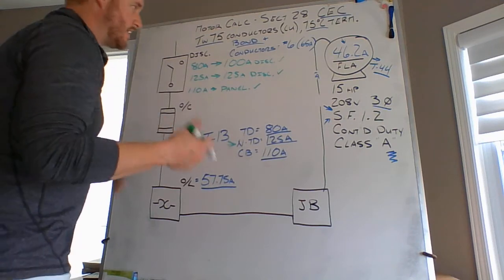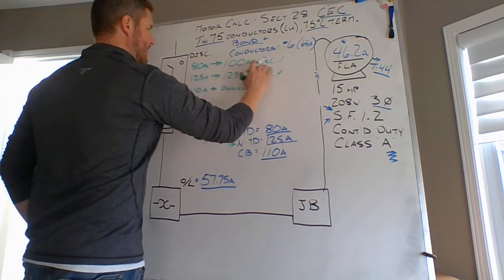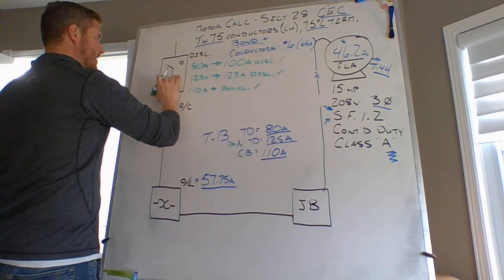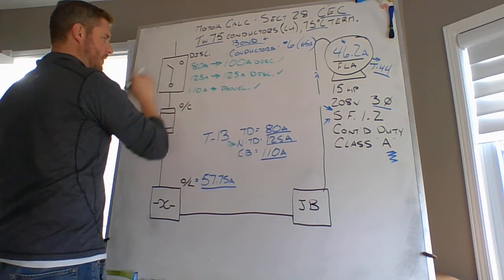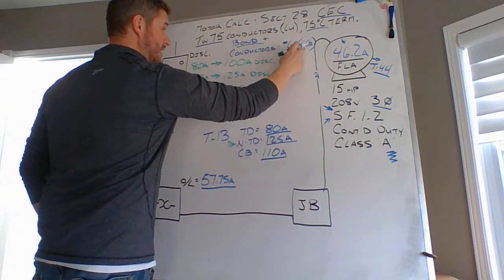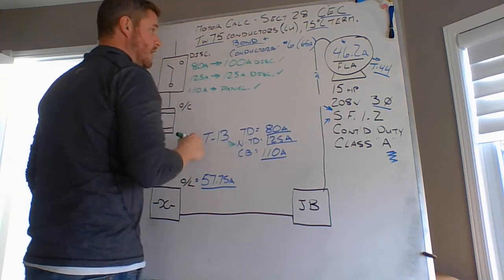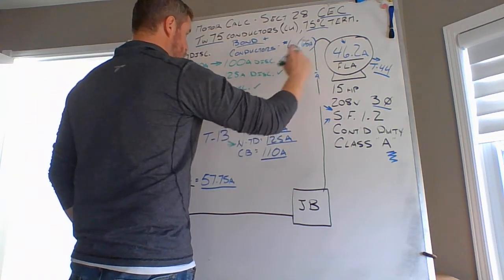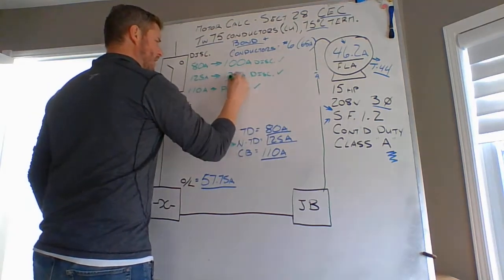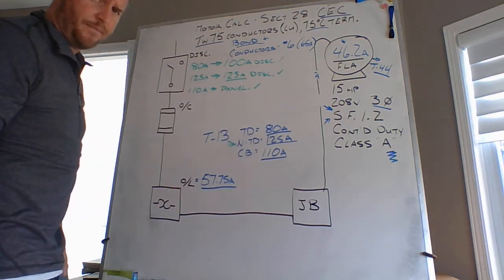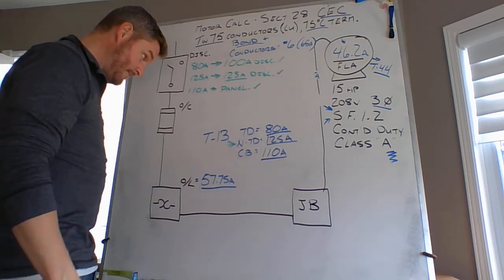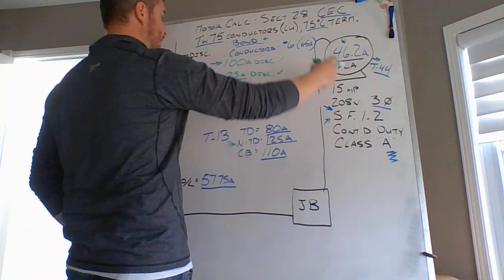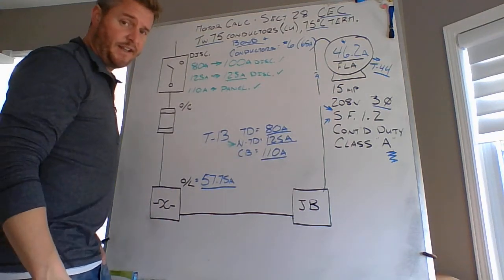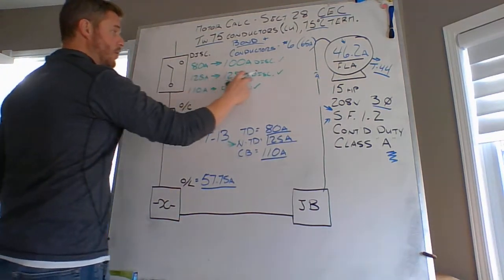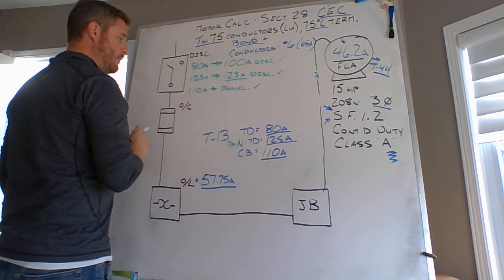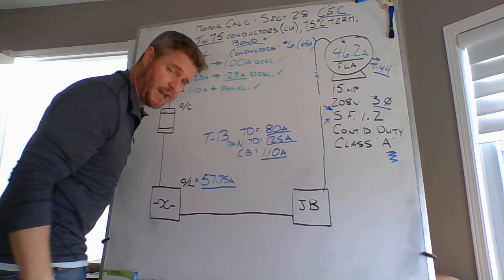But you're actually going to sit there and tell me that you're going to put in a 100 amp disconnect with 80 amp fuses inside this disconnect, 1, 2, 3 of them, with number 6 conductors that are only good for 65 amps to protect a motor that realistically should never draw more than 46.2 amps? On a 125 amp fuse, that's 300% of the full load current rating. You're going to do that installation where you put in a 125 amp disconnect with 125 amp non-time delay fuses, and you're going to connect number 6 to that?